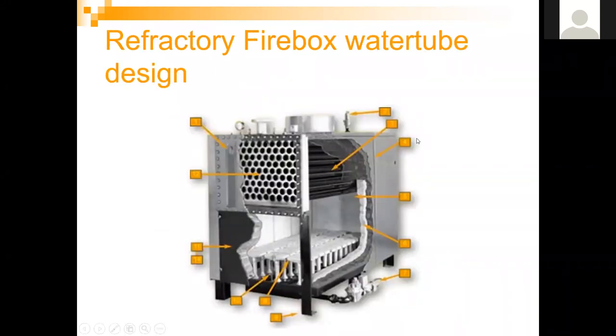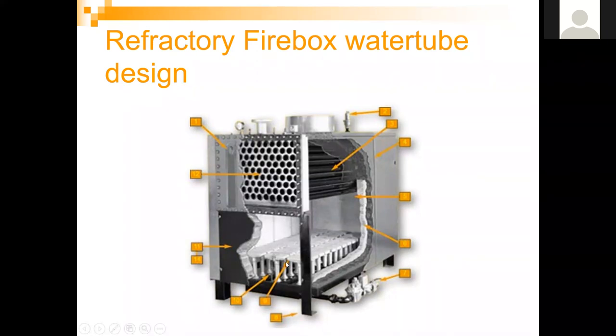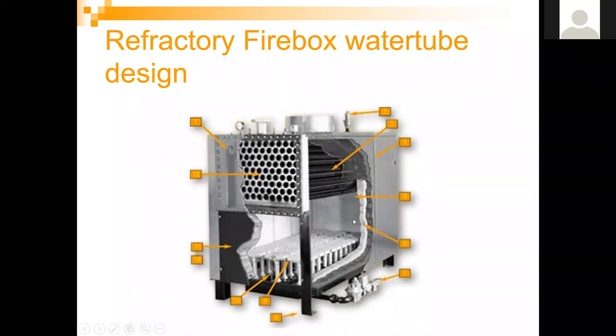This is an older design — Ajax used to make these as a refractory firebox water tube boiler, but stopped making them years ago. It was a water tube boiler using straight tubes, nice from a service perspective because the straight tubes were easily replaced and serviced. The downside was always large cast refractory walls surrounding the furnace, resulting in radiation losses into the room. Those cast refractory walls could also fail and need replacement over time.